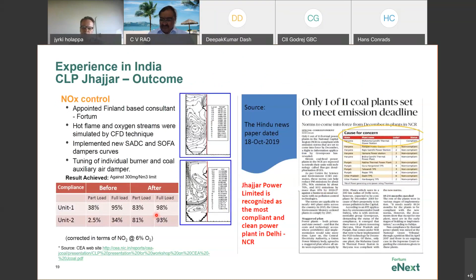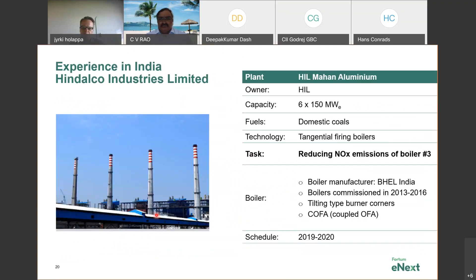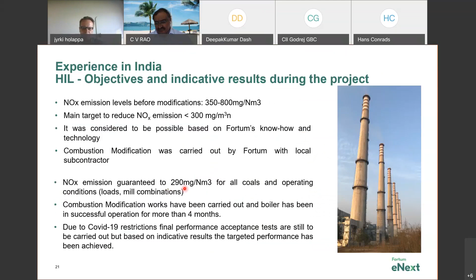Another project we've done is Hindalco, which is still ongoing - a 150 megawatt HIL boiler. There we had very hard conditions: we had to meet 290 milligrams at all loads, all mill operations, and any coal they use, which is Indian coal. Unfortunately COVID-19 has prevented us from doing the final performance test, but based on initial provisional information, during 3 months of operation after the works, we've met under 300 milligrams consistently - these are daily averages. I cannot reveal exact numbers here, but this is a good indication that the 300 milligram limit can be met.